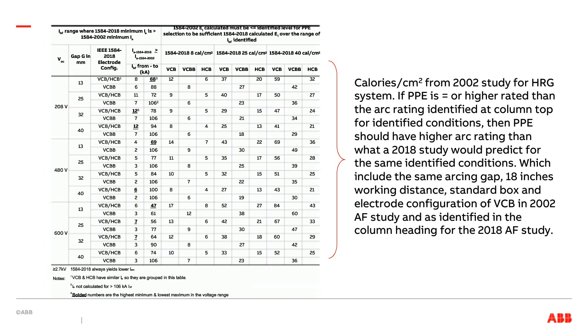This table, by the way, is for an HRG or high resistance grounded system. Before this presentation is posted, I will add a table for solidly grounded systems. But that's the crux of the method. By understanding how your protection is going to respond to the new arcing current, and by making the assumption that your gap, box, and other parameters are not changing, and the only parameter that might change is the electrode orientation, you could create values ahead of time that make sense for your facility.